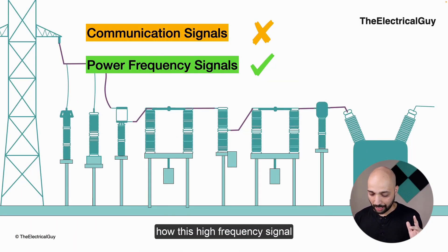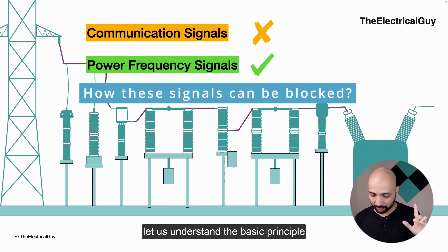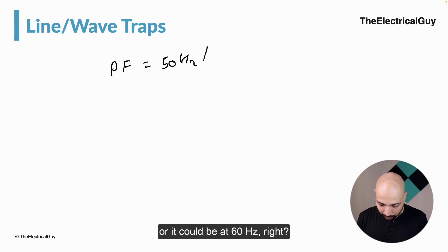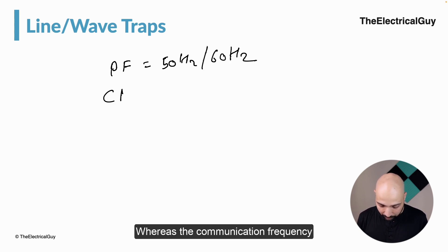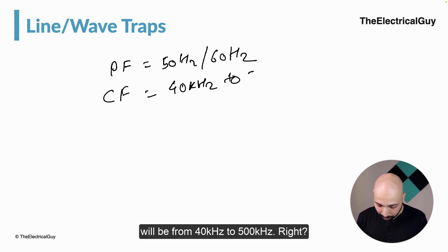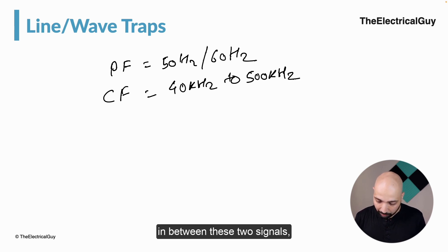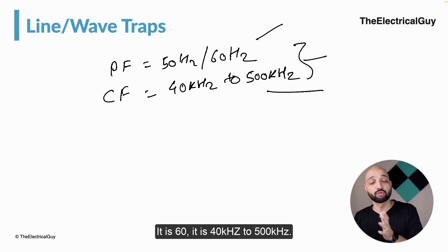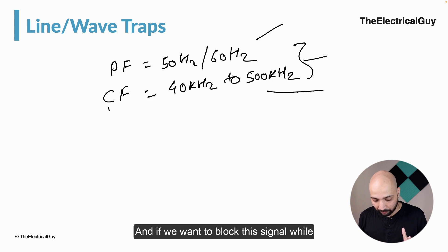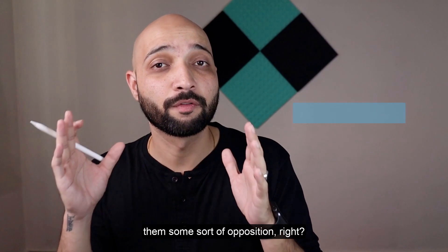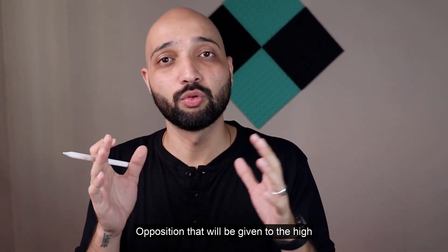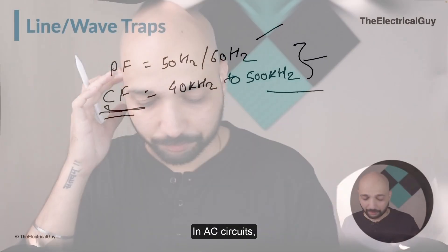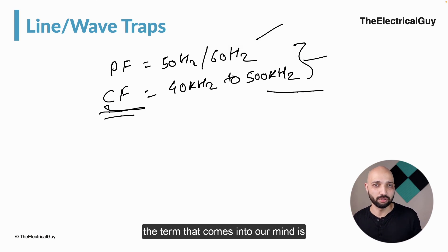The blocking device that does this is nothing but the wave trap, or line trap. Now, how can this high frequency signal be blocked? The basic principle is that power frequency is at 50 or 60 hertz while communication frequency is 40 kilohertz to 500 kilohertz. We need to provide opposition to the high frequency signal without offering opposition to the power frequency signal.